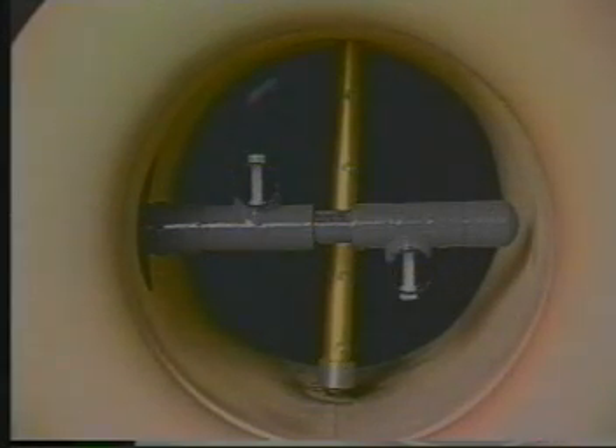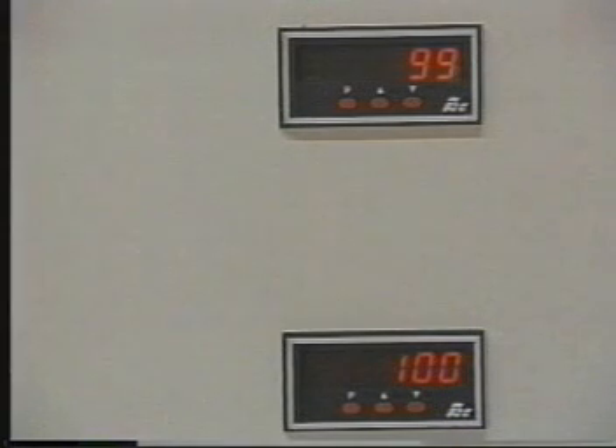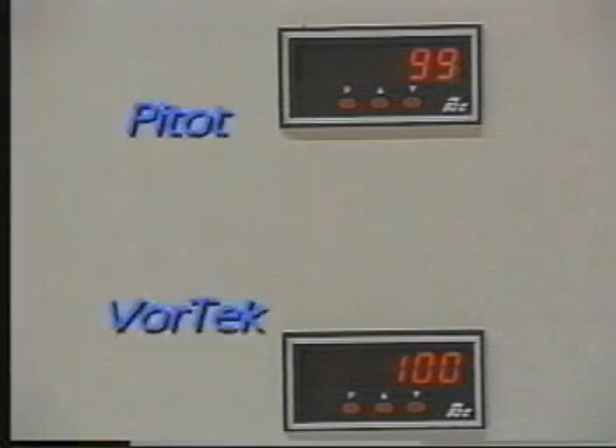With the vortex sensor, the signal changes in direct proportion to flow velocity. With Pitot or orifice-type devices, the signal that is measured changes in proportion to the square of the flow. When flow velocity is reduced by 50%, vortex indicates a proportional output of 50%. The new reading for the Pitot sensor is 25%, the square of 50%.